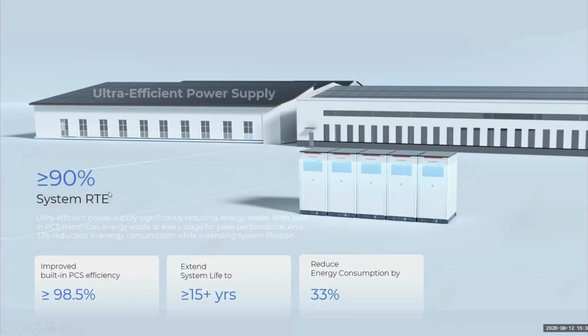Even these cells can supply the cycles for the 8,000 cycles, but for the BESS, we not only discuss the battery cells, we also consider the BMS and the whole system integrated, from the modular design of the battery module, to the liquid cooling machine, to the PCS. So all the internal components can support a system life of at least 15 years. This is at one cycle per day.